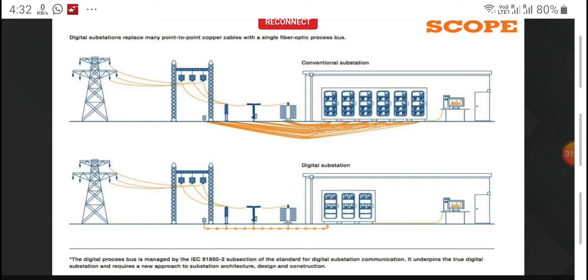It can connect with the bus, and all these signals are shared by everyone. And you can see that the number of control panels also reduced. Instead of what you used to do for feeder protection or line protection, you have one panel for the control panel, one is the relay panel. In the control panel, BCU and all other control systems or meter system will be in one panel. The second panel is more dedicated to protection, where you see the main one relay or main two relay or backup relay or their auxiliary relays, LBB relay, and all other relays normally lie in the relay panel.